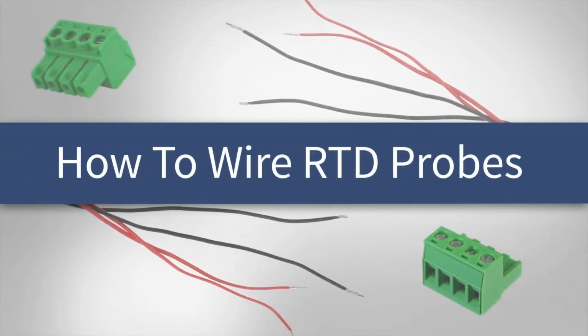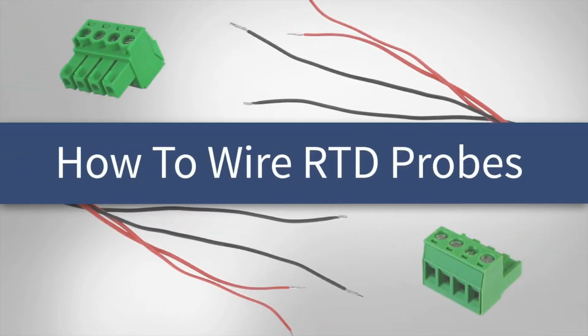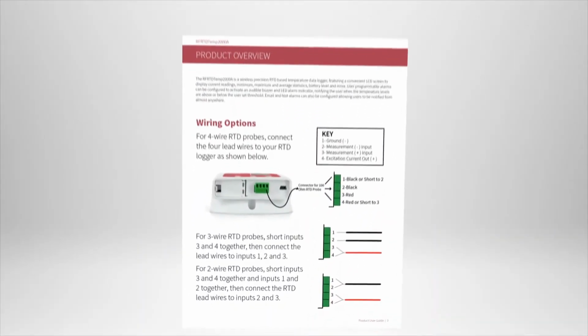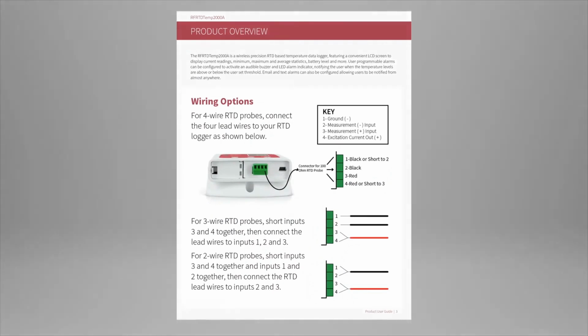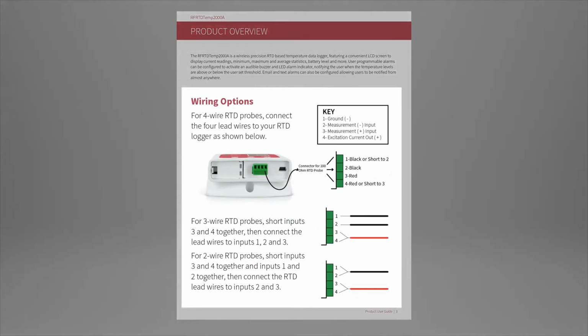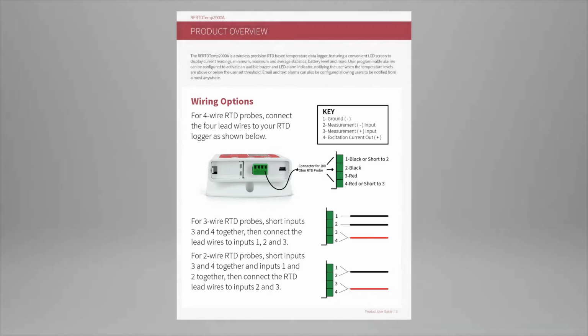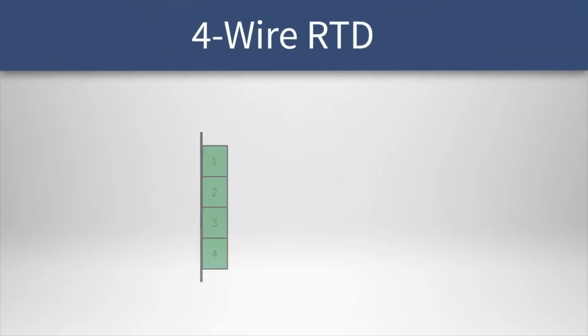Today we'll be covering how to connect or wire your RTD probe for use with a data logger or other measuring instrument. Before we begin, please refer to the manufacturer's wiring diagram as the color coding may vary between suppliers. The probe's documentation should indicate the use of each wire if the wire colors do not match our typical black and red examples.